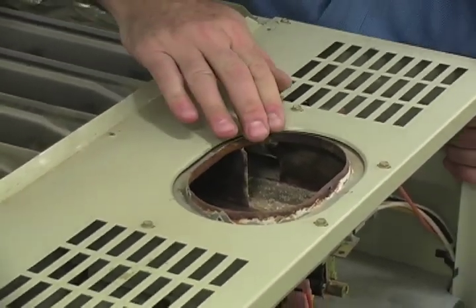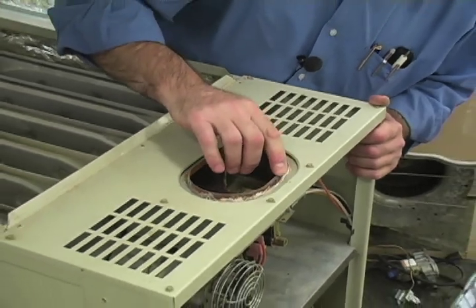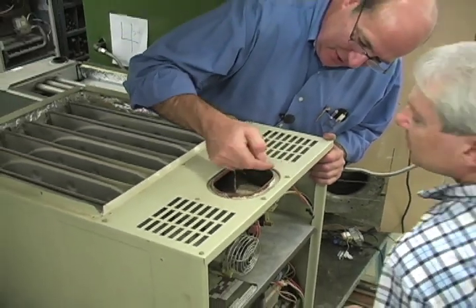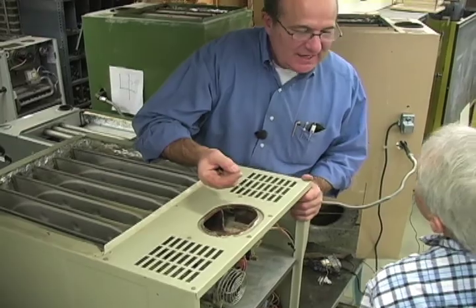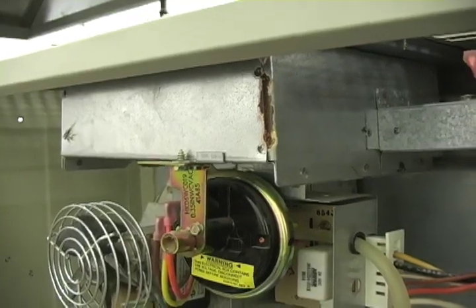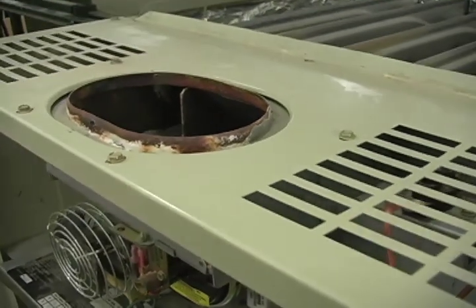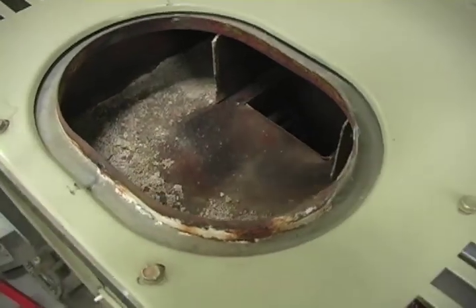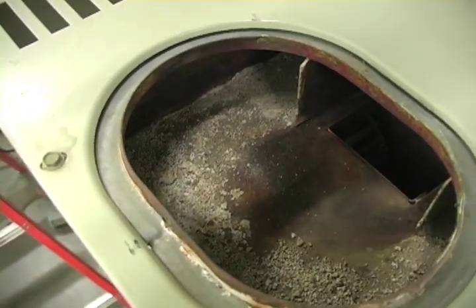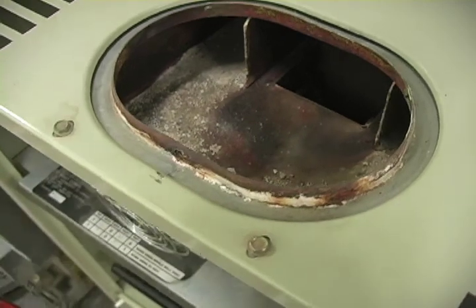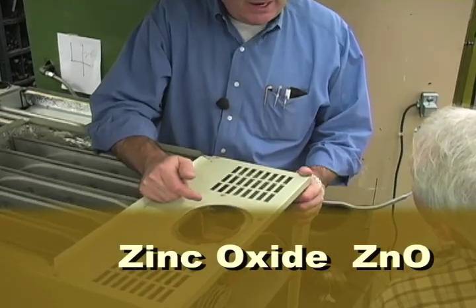This flue connector here is showing quite a bit of corrosion. We can see some white deposits over here. No doubt that's zinc oxide. These types of furnace collars, the flue collar on here, is typically connected to the exhaust system or the chimney system by a single wall galvanized metal pipe.